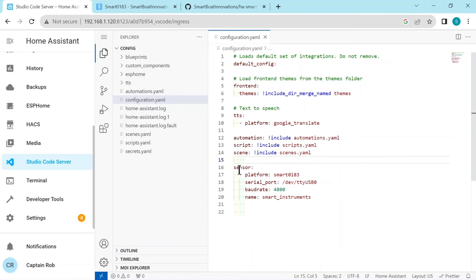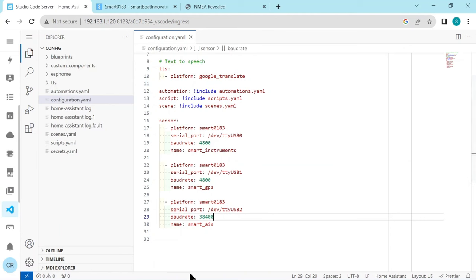Now, so this defines that's using the platform, the integration Smart 0183, the serial port is the one we've checked - it was the TTY USB 0 - and it's 4800, that's the speed. Now if you have other instruments, you can actually connect them like this: you can say it's TTY USB 1, USB 2, and you can put different baud rates under the same sensor, so you can have multiple inputs. But for this demo we're just going to use the one USB 0. So then save the configuration YAML.